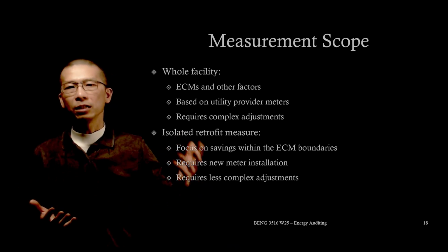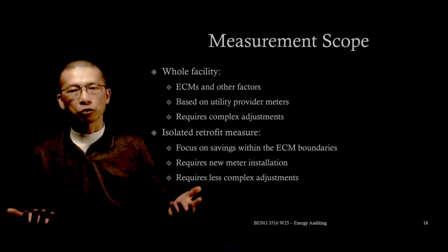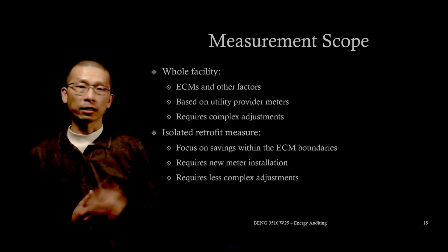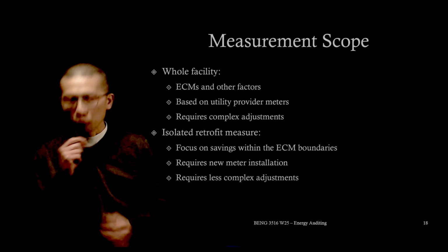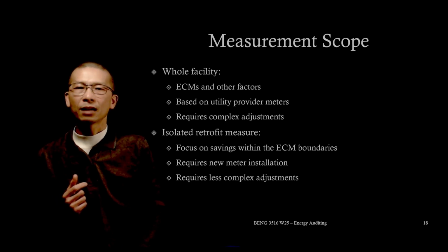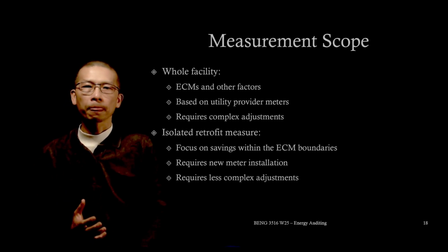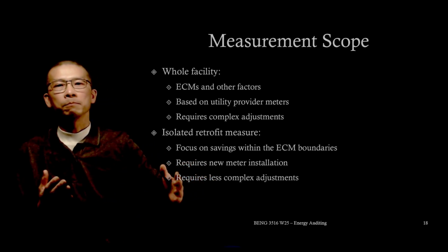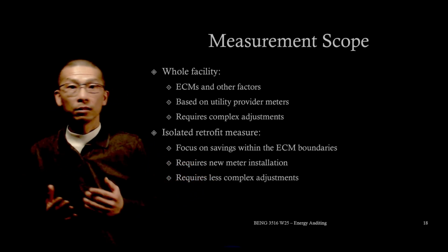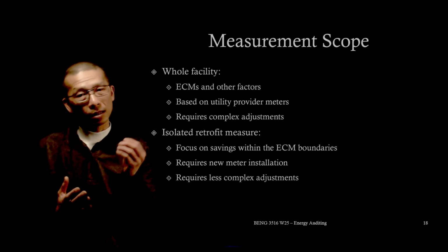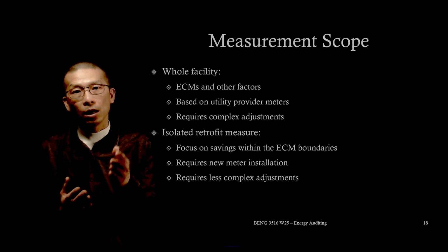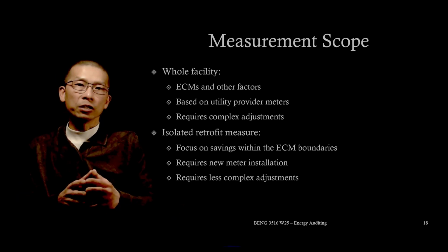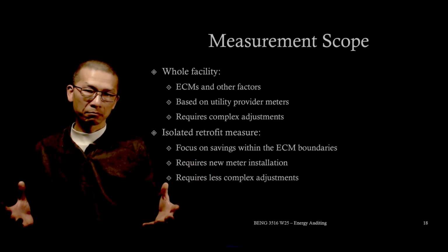Well, we use the utility provider's meters: electricity, gas, water. The challenge here is it requires complex adjustment to separate ECM savings from other factors. It's not easy to pinpoint which ECM is performing best. We only know the total impact.